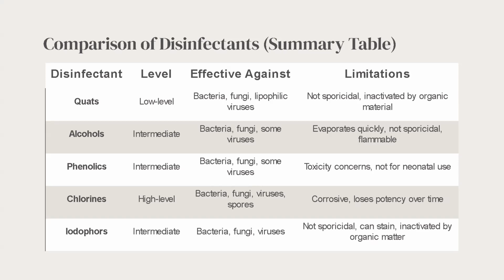Then we have the iodophors, also intermediate. It works very well on bacteria, fungi, etc. But it is not sporicidal. Can stain, inactivated by organic matter. But when you look at almost all of them, organic matter is a concern, which again boils down to the fact that when you're working in the decontamination room, you must make sure that you really clean the instruments, because when they are not well cleaned, they are going to hinder the effectiveness of some of these disinfectants. Very unfortunate, but that is the situation.